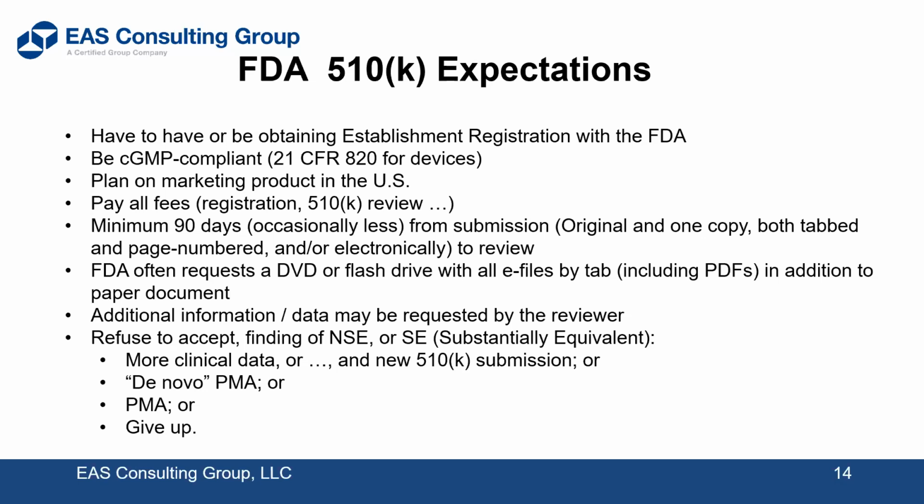510Ks are supposedly cleared within 90 days. I've had one clear in 30 days, and it was a traditional, not a special or abbreviated. But in most cases, it takes longer than that, usually 120 days or so. That's what I usually tell clients as well. And I gave you an example of one where the FDA required clinicals, and that dragged out for almost a couple of years. PMAs can take a couple of years and cost considerably more because you're dealing with a lot of clinicals in most cases.